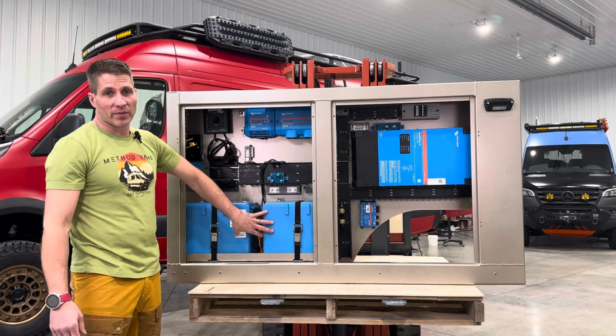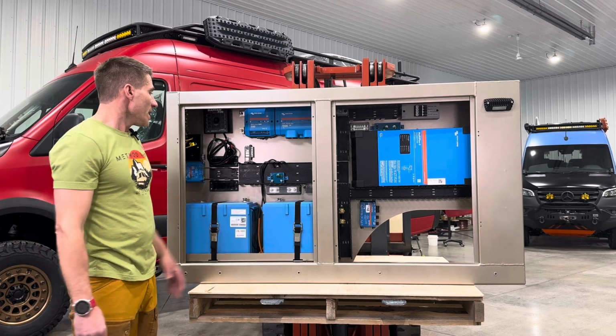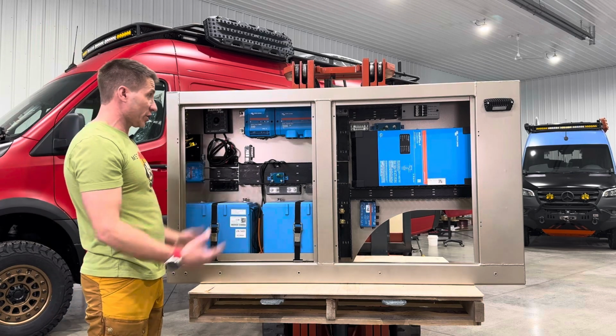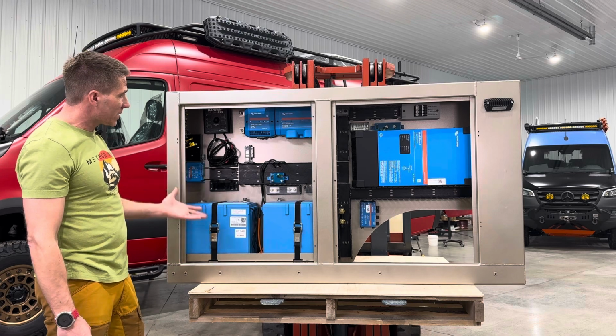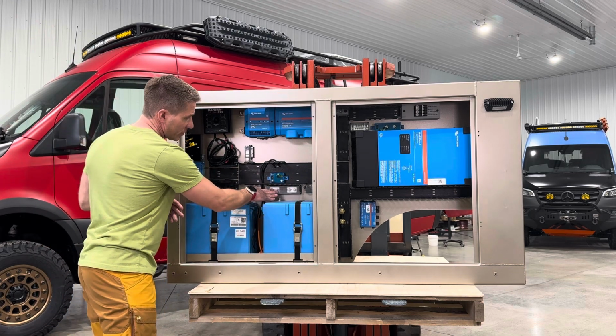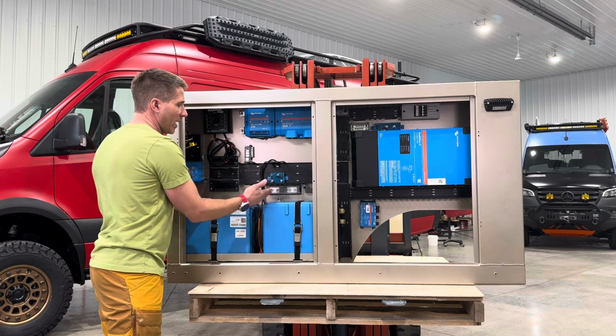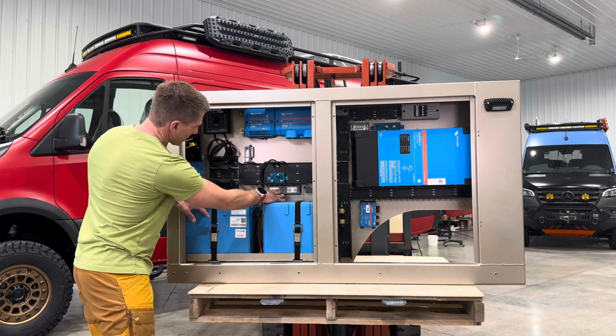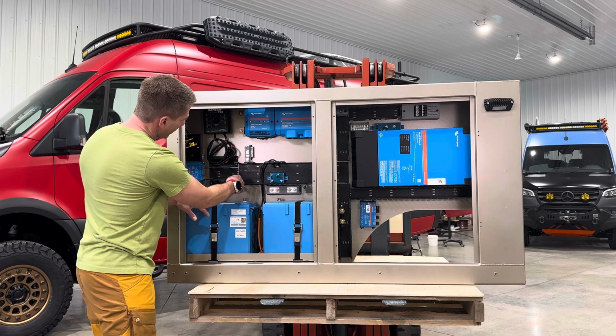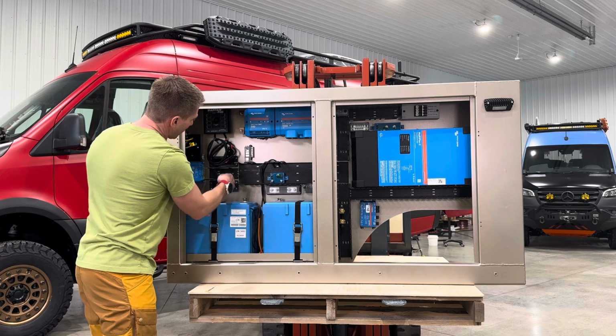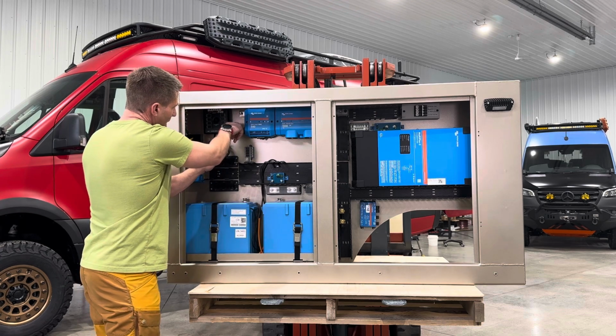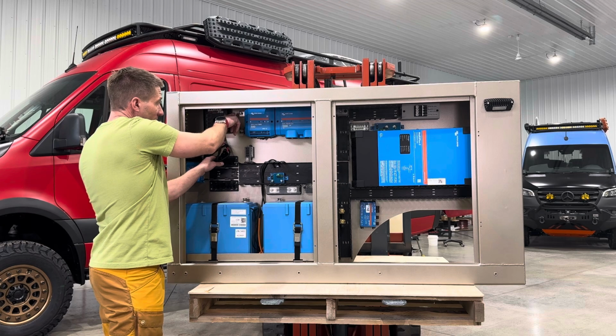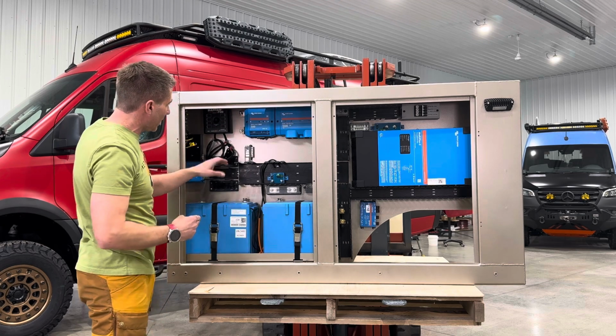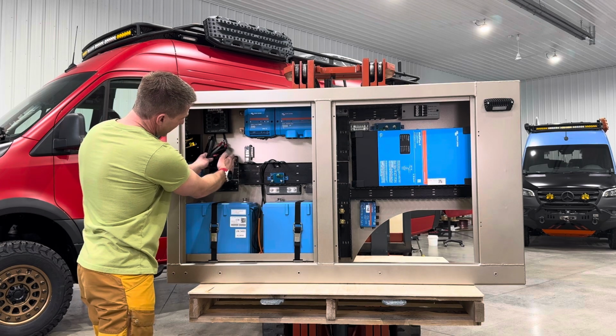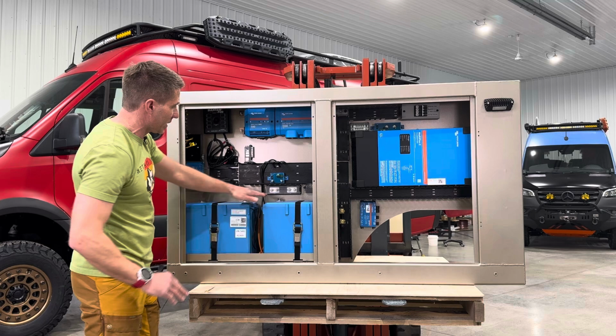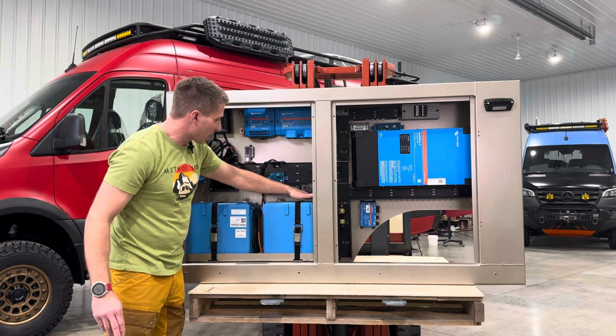This is the beast of our system. We have our batteries, and from there they can do a whole bunch of things. Everything in our battery system is fused. Our main fuse, a 400 amp fuse, comes through - as you can see, it comes up perfectly to the negative, and the positive goes up into the positive. We use a creative 90-degree lug so we get offset between the positive and negative. The positive laces down here, drops right through into the blue Class T fuse, then connects into our batteries.